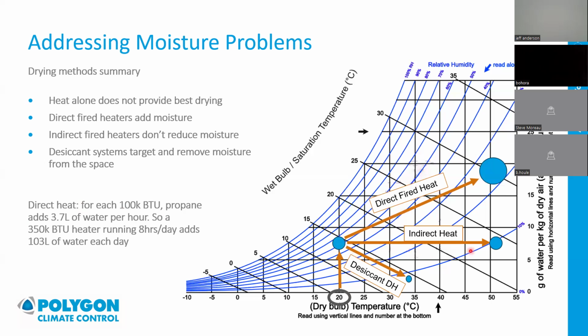So with indirect fired heat, rather than getting all that CO2 and other byproducts, we're just getting heat. We could go from 20 degrees to 50 degrees, making it very hot, because it's really good at heating air. But your little blue ball stays the exact same size. Your relative humidity drops because you're expanding that air, and as air gets hotter it can hold more water. So your relative humidity might drop to 10% RH, and someone might look at the site and think you did a good job drying it. But your vapor pressure hasn't changed at all. It has the exact same amount of water as before, so if your vapor pressure in the air matches your materials, they won't dry.